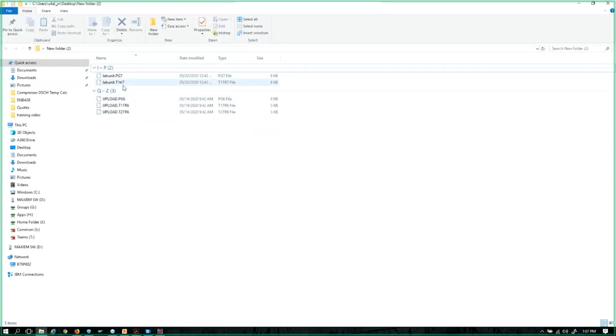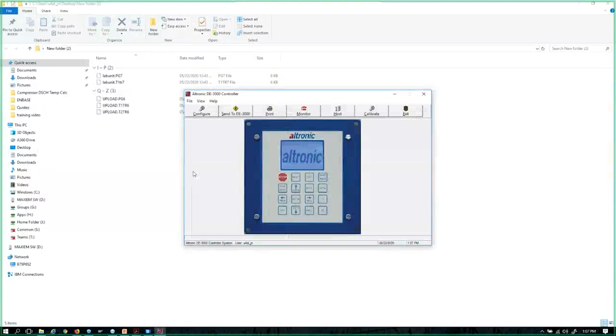The 7 identifies if it's a version 2X. The 6 identifies that it's a version 1X. The T1 identifies the primary or number 1 terminal board. A T2, a secondary terminal board, and that terminal board could be a 15 channel or a 30 channel. We don't know until we open up the program. And then the PG obviously indicates that that's the file for the display system. So with that, I'll return back to the software.